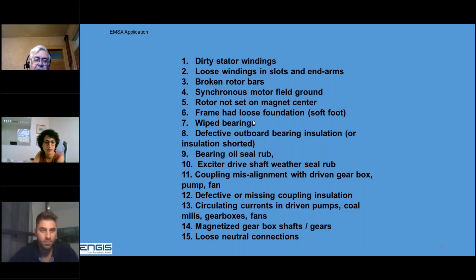Loose foundation, white metal bearings. Outboard bearing insulation on most large motors is insulated. That can fail or short. You can get a seal rub. Again, the sniffer tells you exactly where to look. Now, the sniffer won't tell you whether it's a bearing insulation problem or a seal rub, but it will tell you to look at that bearing. So when you open it up, you can find what the problem is.